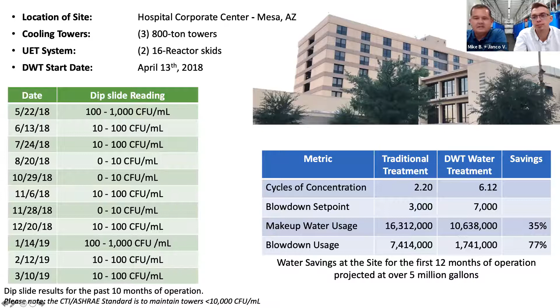The blowdown set point is actually your conductivity set point. 3,000 microsiemens for Arizona is not significantly high, it's pretty typical. We moved it to over 7,000. The measured savings was 35% overall water and a 77% reduction in blowdown.